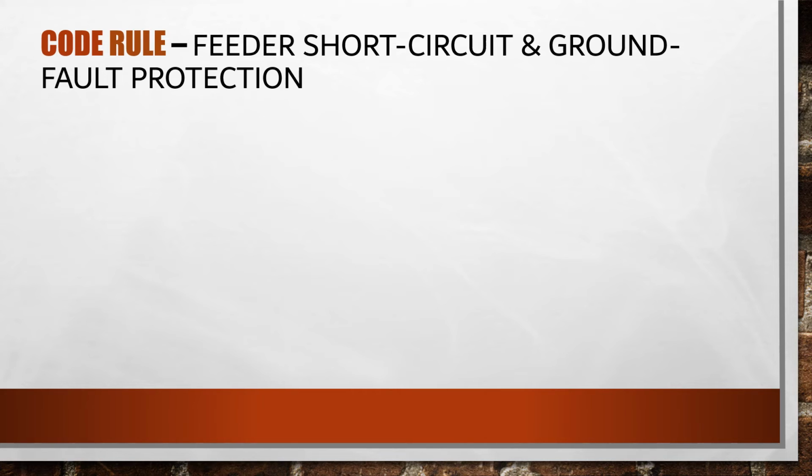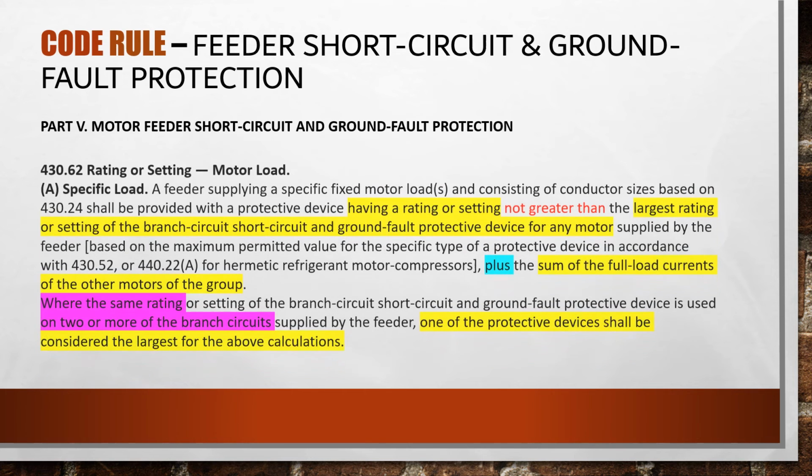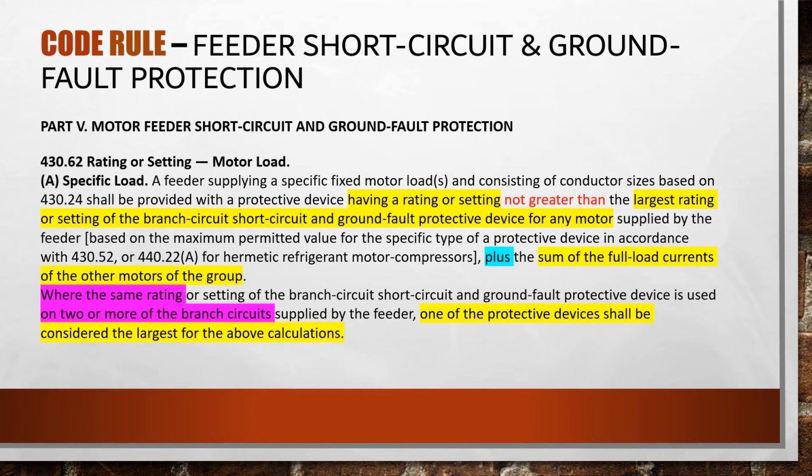Now for the code rule for the feeder short circuit and ground fault protection, or the circuit breaker. Motor feeder short circuit and ground fault protection, Part 5 in NEC 2017. This provision states that to calculate the short circuit and ground fault protection, we have to add the following.